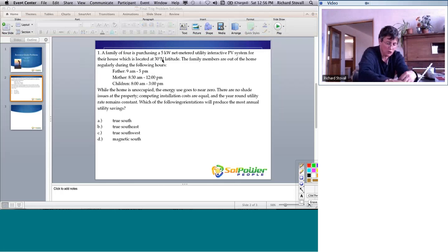What does this tell you? As you go southeast or southwest, again, a slightly steeper orientation, you lose a little bit. As you get towards plus or minus 90, meaning due east or due west, look at the difference there. And at plus 20, which would favor a winter sun situation, on a yearly average you only get 67% of what you would have had if you had it tilted at latitude, whereas making it flatter, you lose a little bit. You actually get better production than if you had it at latitude, if you're facing the west.